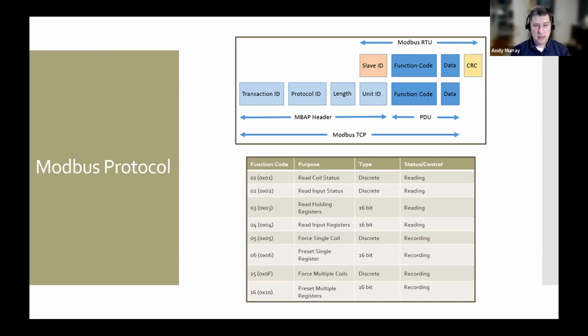But in the message, there will be these function codes, which basically tell the end device or the SCADA server what kind of message is here. So maybe function 01 will allow you to read coil statuses. The SCADA server may send that message down to a device and say, tell me, are all your 3 breakers open or closed? And it will send back binaries for each one of those, a 1 or a 0 for open or closed. There may be another one for reading the analog values, things like that.